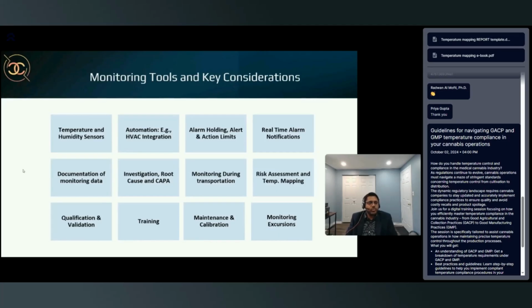So alarm holding allows you to actually hold your alarm for a certain period. So if you're setting, for instance, 1 or 2 hours for your relative humidity, for temperature, you cannot go 1 or 2 hours. You do not have the liberty to have a very high temperature, whatever the temperature range is, or a very low temperature for 2 hours. Plants will be very susceptible to a very high temperature range. That's why you might want to consider maybe 10 minutes, 15 minutes, even if you set an alarm holding for temperature. Now, what are alert and action limits?